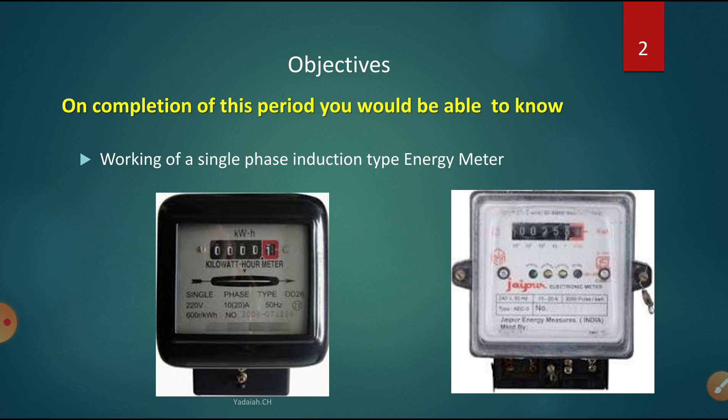We are required to stop the device. The deflecting torque is produced with the help of the driving system, and the aluminum disc rotates. We are going to control the rotation of the aluminum disc with the help of the braking system. For this purpose, I have used two permanent magnets placed at opposite sides diametrically. By adjusting the magnets, the speed of the aluminum disc will change.